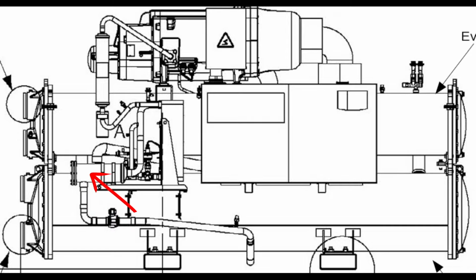Anyway, come up into our filter dryer, right? So this is probably a 2 cartridge dryer, looking at the size of it, unless they did one of their screen things where it's partially dryer, partially screen. So maybe just 1 core in there. It's a 1 or 2 core dryer. Here's the plate to open it. This is your inlet, outlet. So we come out of our filter dryer up into the top of the braze plate.